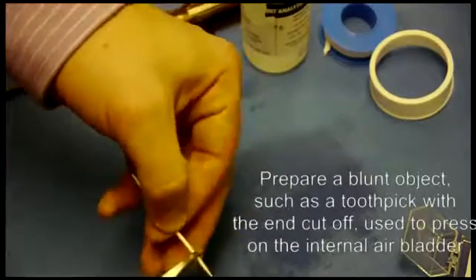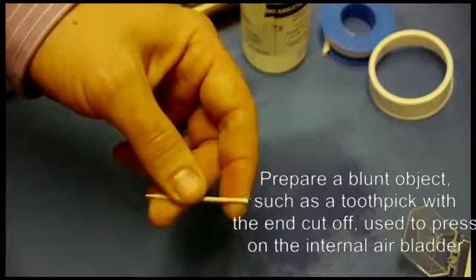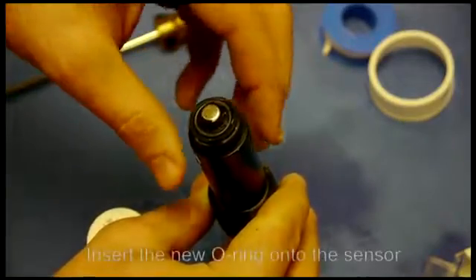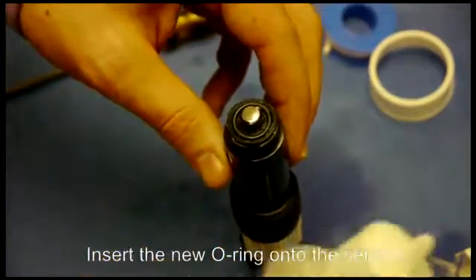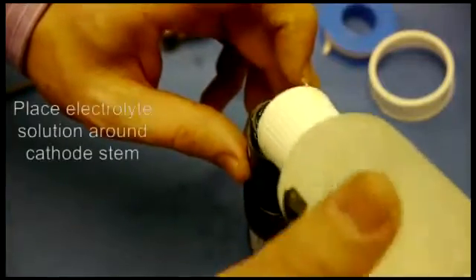Next get a toothpick and snip the end of it so it has a blunt end that you can use to press the air bladder in the cathode. Take your new o-ring, place it around the stem of the cathode, and then use fill solution and cover the tip of the cathode.